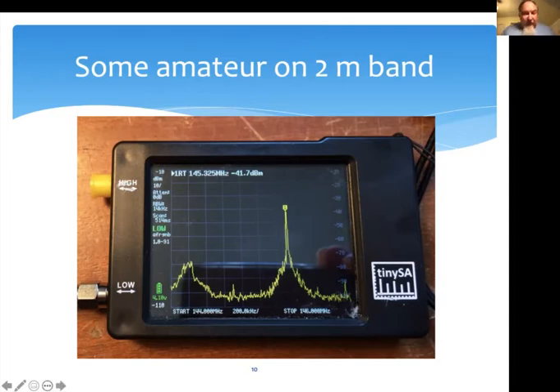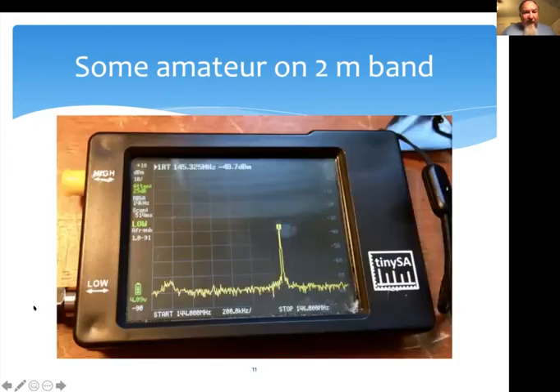So next experiment, engage the internal attenuator. If you look on the left-hand side of the screen, you now see that the word atten is in green, which means the attenuator has been engaged and it's attenuating the input signal by 25 dB. And this has pretty much cured the problem. That skirt that you saw before, the 300 kilohertz skirt, it's not real. It's an artifact generated because the signal input was just too high. Now, if I'm only measuring the frequency, it doesn't matter.